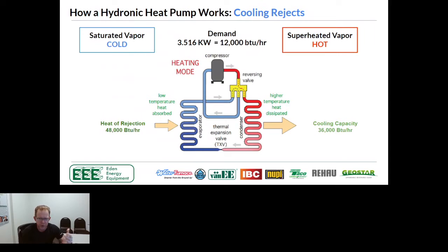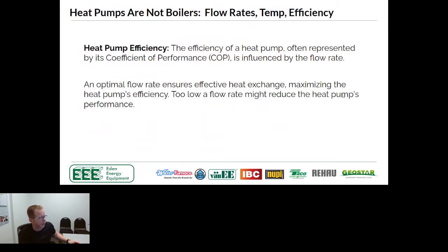So the way that this is done is pretty simple. Obviously, it has a compression circuit, it has a reversing valve that shifts inside of the unit. But in the bare principle, this is how an air to water or a water to water would work from the inside. So we talked about this before. One of the key things that we want to be paying attention to is COP. Obviously, whether it's a heat pump or a boiler, we want to make sure we pay attention to our flow rates and our temperatures because that dictates our efficiency.